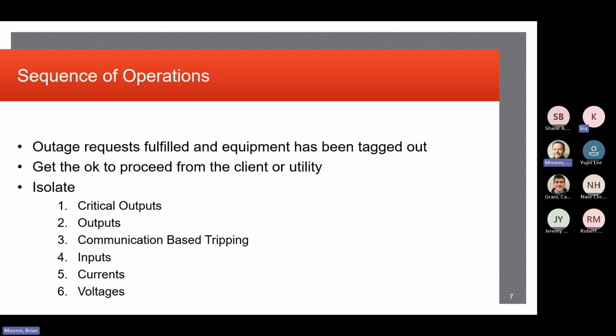If you do open a current or voltage, your communication-based tripping, you could isolate your fiber optics, or you could turn off a switch that would disable a protection scheme. Any inputs, it could be breaker A fingers, it could be anything that's wired in. Again, inputs are part of the logic diagram too. Voltages, currents, and an input or a series of inputs in any AND or OR combination also drive logic. So it's important to open that stuff in this order of operation.